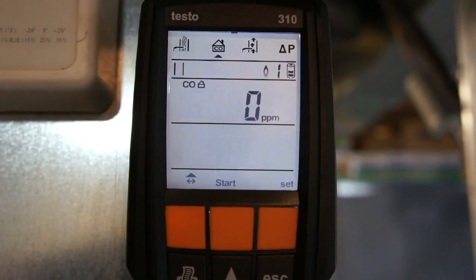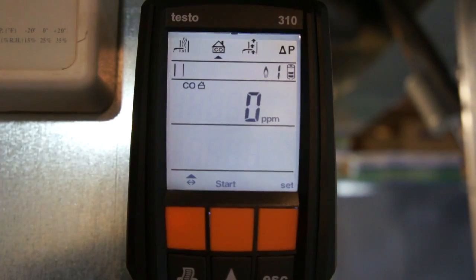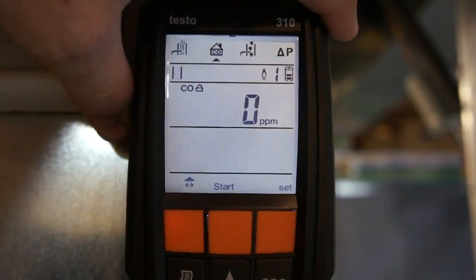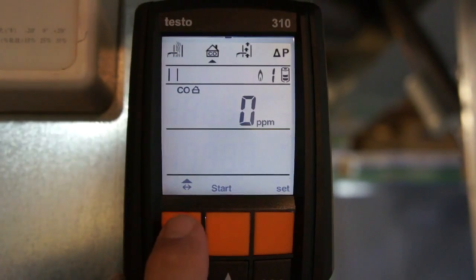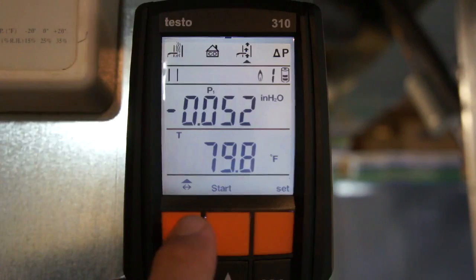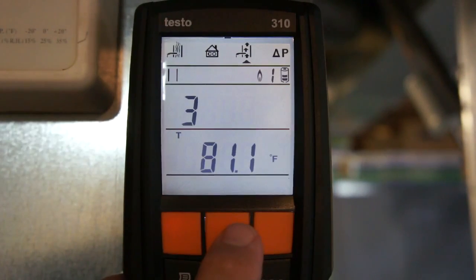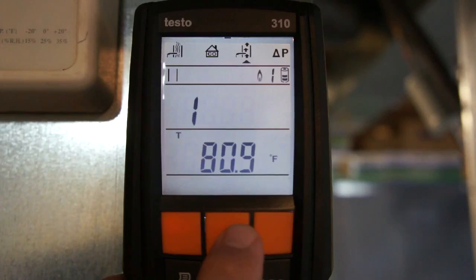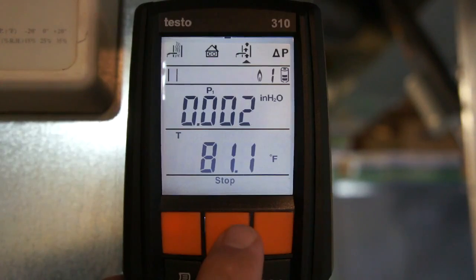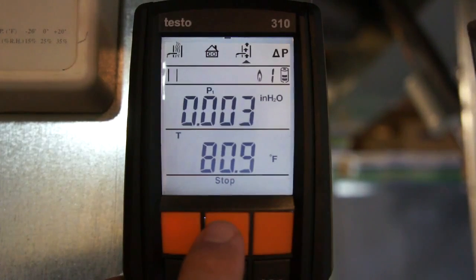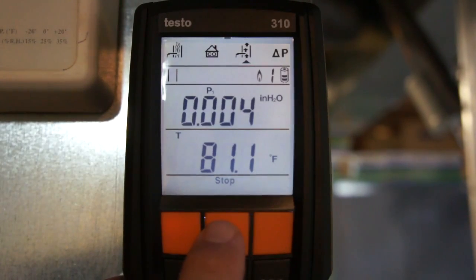We're in the ambient CO test mode and we've assured there's no CO in the space. Now let's say we want to do a draft test on our furnace and make sure we have adequate draft before we do our combustion test. I'm going to push the left-right arrow key and toggle that over to my draft reading. I'll push start and it's going to go through a five-second stabilization period for the manometer. The probe is currently out of the draft — I'm going to show you how to get a reading on that.